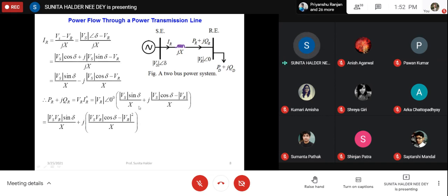Using VR times IR conjugate, we can get the active power and reactive power. Active power is VRVS by X sin delta, and reactive power is as derived. Delta should be positive, meaning Vs must be leading Vr. If delta is negative, power transfer will be negative, meaning power transfers from the receiving end to the sending end, not the other way.